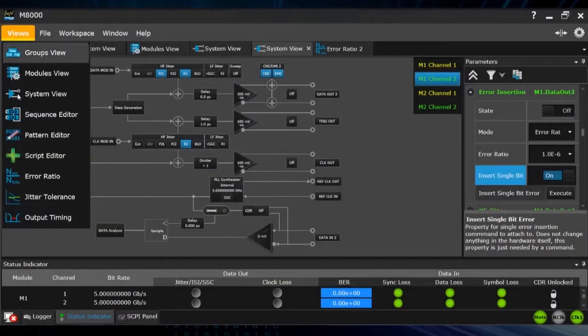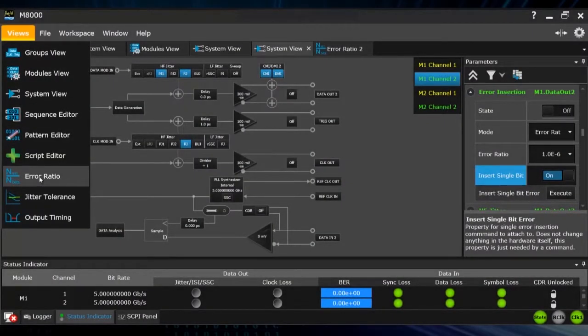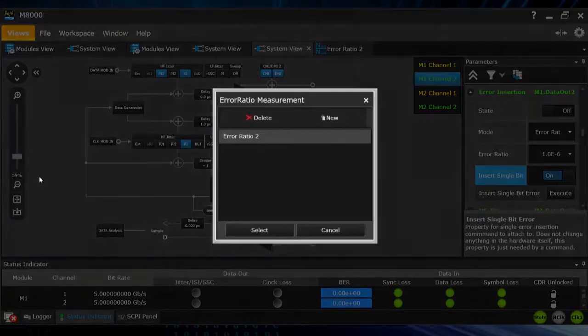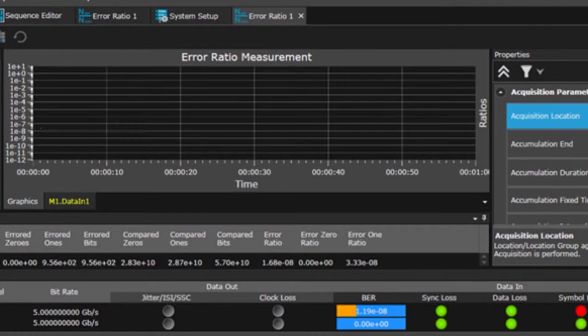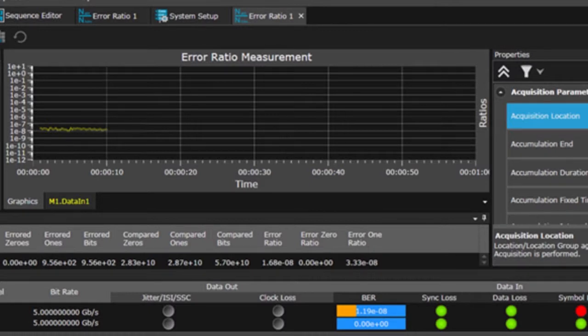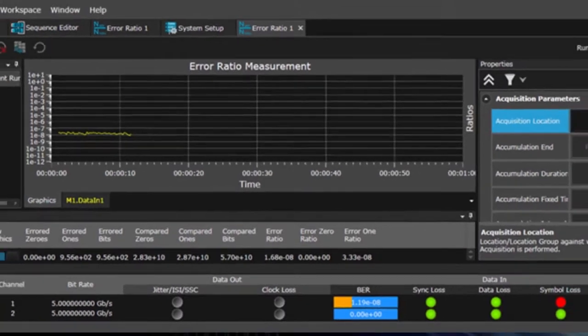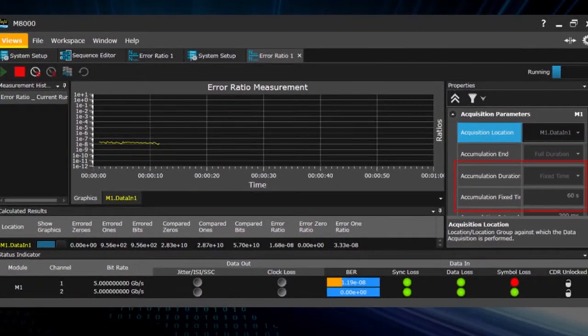Now I can show the analysis capabilities of the new J-BERT M8020A. You have here the choice of monitoring the bit error ratio. So when I start to insert errors, you can see the errors here over time. You can scale the timeline that you want to check.